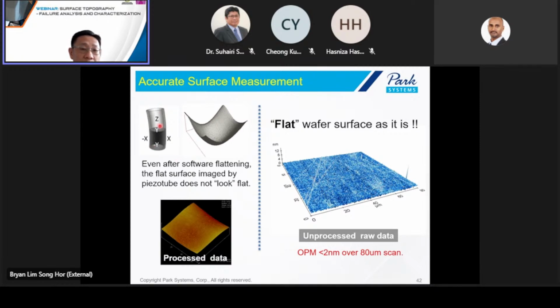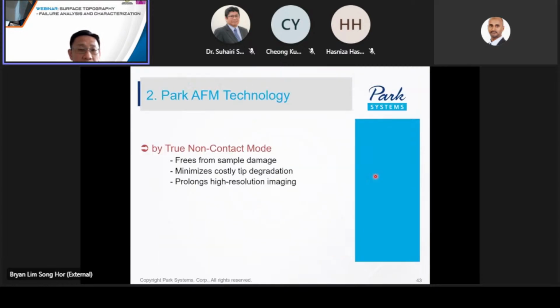So this is a tube scanner. There may be a bowing effect by the piezo. So even after the software flattening, the image does not look really flat. However, with this decoupled design, we have a very flat scan. Right, so the out of plane motion is very low, very flat scan, very uniform scan. So this is one of the technological advantages of Park Systems.